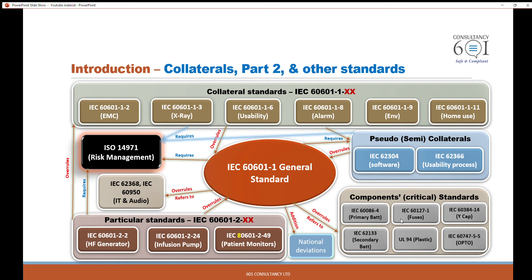Basically, when you have the components certified, it will make it easier to meet the requirements of the general standard. We also have the IT and audio equipment standard — IEC 62368 and IEC 60950. IEC 62368 replaces IEC 60950, so IEC 60950 is the former standard. For example, if you are employing a monitor, an iPad, a power supply unit, or any IT equipment, you will need to meet the requirements of the IT and audio standard.